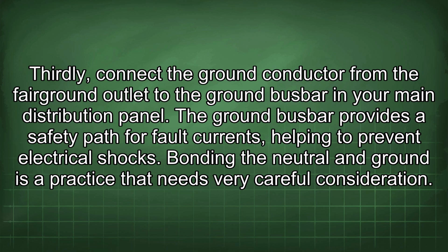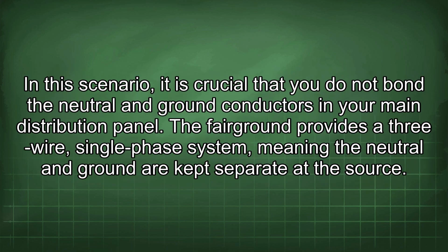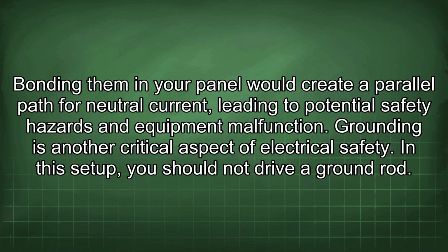Bonding the neutral and ground is a practice that needs very careful consideration. In this scenario, it is crucial that you do not bond the neutral and ground conductors in your main distribution panel. The Fairground provides a 3-wire, single-phase system, meaning the neutral and ground are kept separate at the source. Bonding them in your panel would create a parallel path for neutral current, leading to potential safety hazards and equipment malfunction. Grounding is another critical aspect of electrical safety.